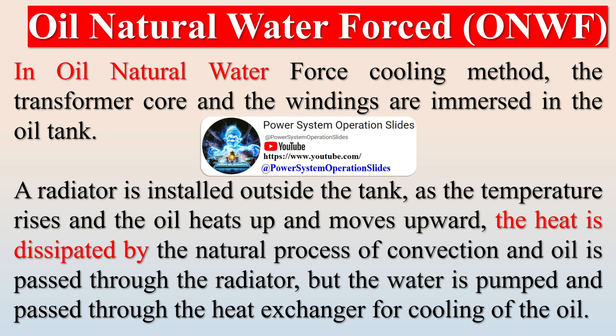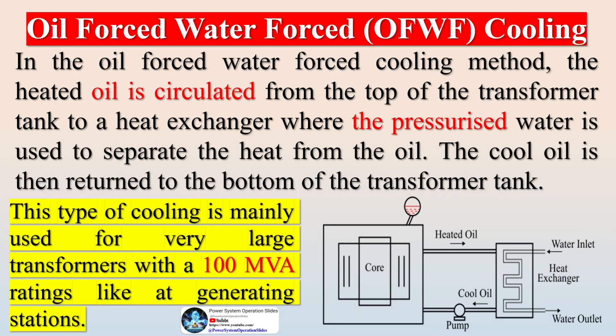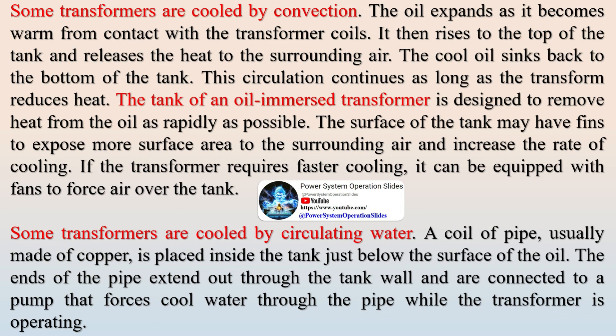Oil immersed water cooled transformers use either Oil Natural Water Forced (ONWF) or Oil Forced Water Forced (OFWF) methods. In ONWF cooling, the transformer core and windings are immersed in an oil tank; a radiator is installed outside, and as the oil heats and moves upward by convection it passes through the radiator, while water is pumped through a heat exchanger to cool the oil. In OFWF cooling, heated oil is circulated from the top of the tank to a heat exchanger where pressurized water separates the heat from the oil, and cool oil is returned to the bottom. This is mainly used for very large transformers rated around 100 MVA, such as those in generating stations.